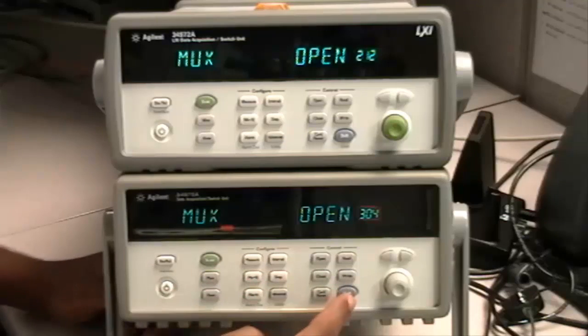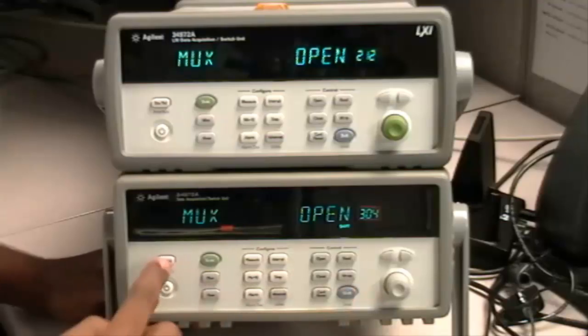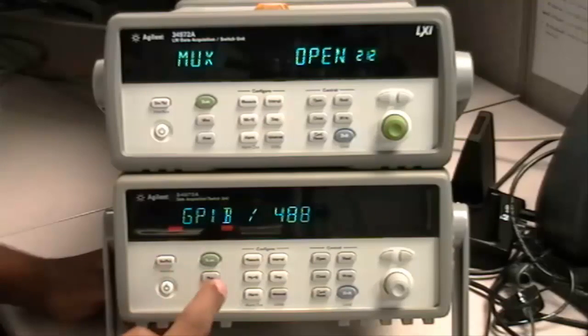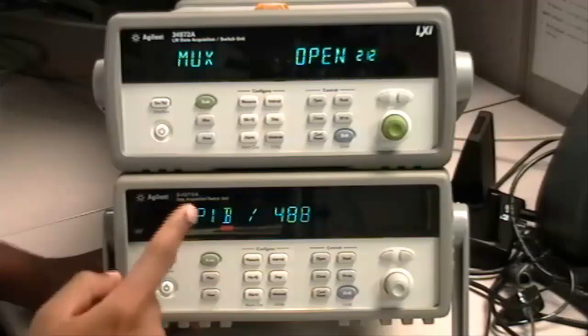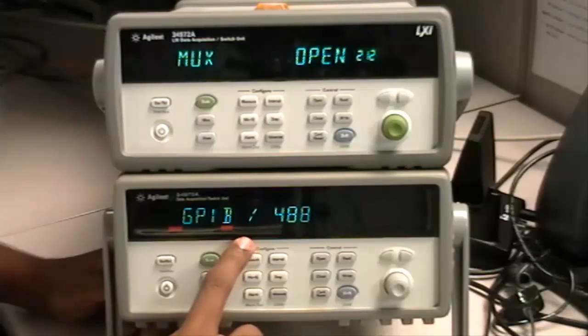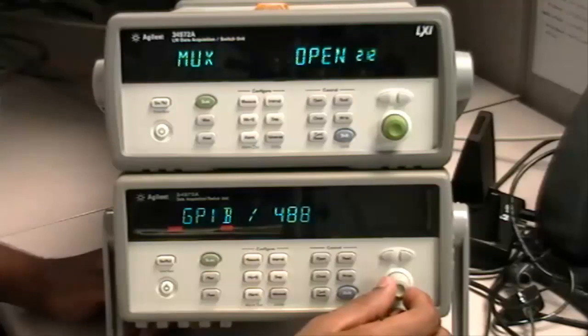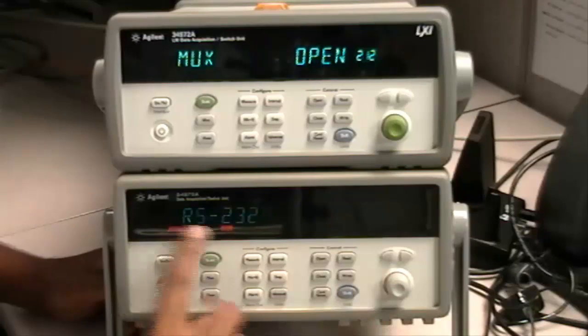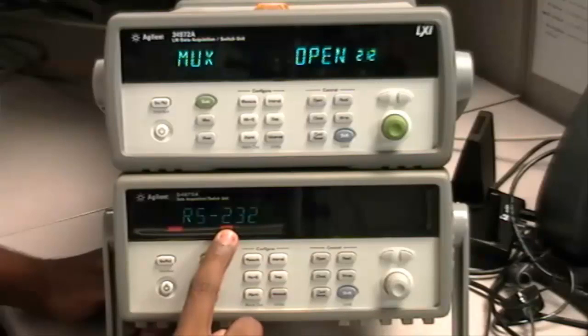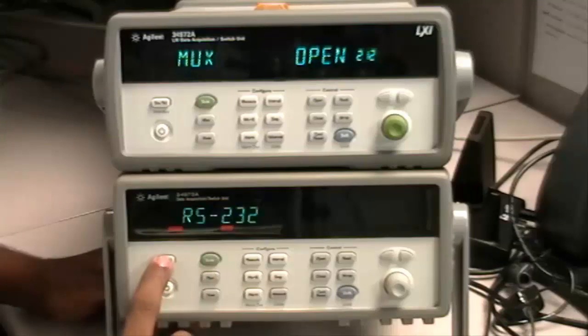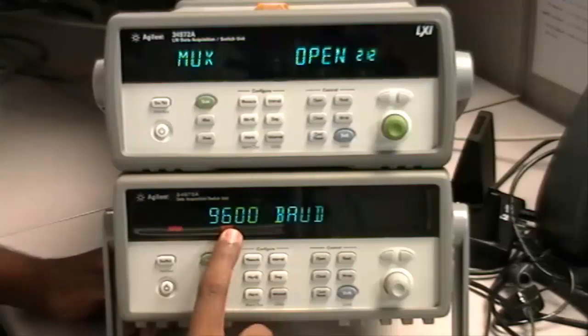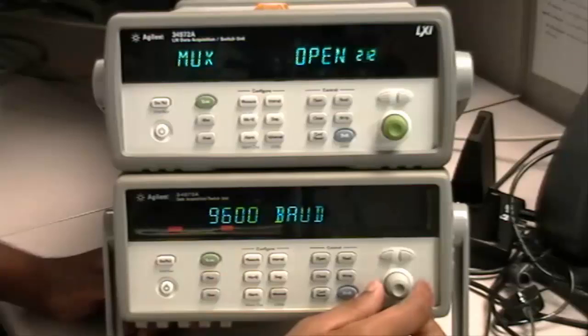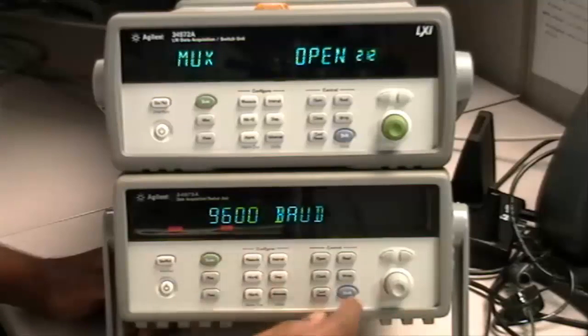What you would do is hit Shift Local and then Store Recall. Right now it's set to GPIB and you can see that RS-232 is in a lighter color. So if you select it, it will become the brighter one. Next, you can set the baud rate.